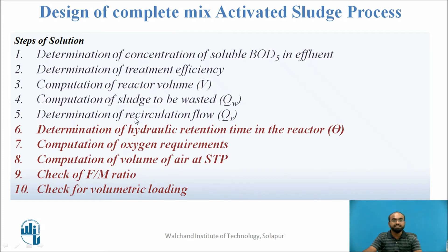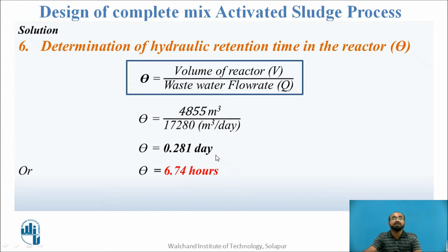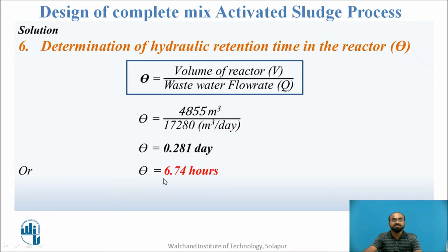We have completed the first five steps and now we address the last five steps. Step 6 is the determination of hydraulic retention time (theta) in the reactor. Theta equals volume of reactor (V) divided by wastewater flow rate (Q), with Q converted to m³/day. That gives 4855 m³ divided by 17,280 m³/day, which comes to approximately 0.281 days, or 6.74 hours.